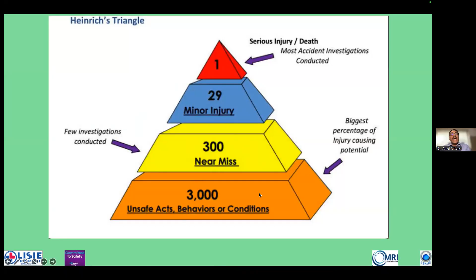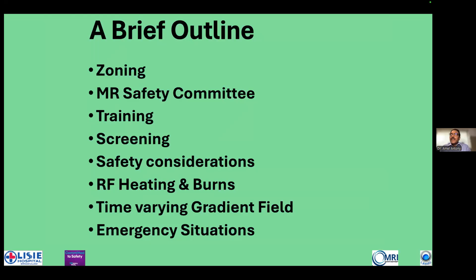Just to have an overall picture, we'll talk about the zoning, what is an MR safety committee, the training required, the screening which is required, the safety considerations, the RF heating and burns, and finally the time varying gradient field and emergency situations. Now, to start off, any MR safety protocol should have what is known as zoning. Zoning means we have 4 zones for any MR equipment to be installed.